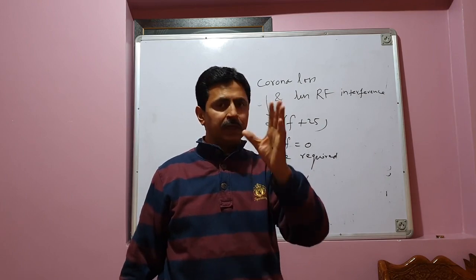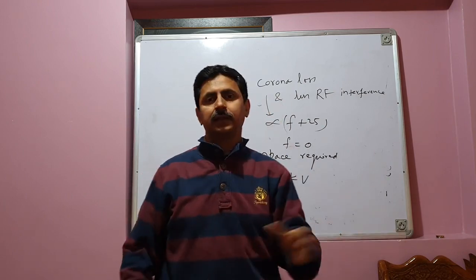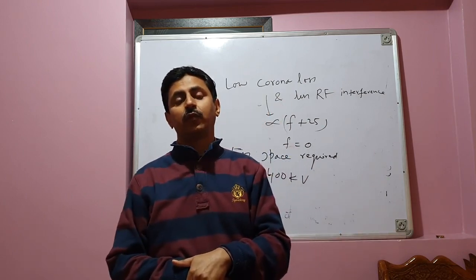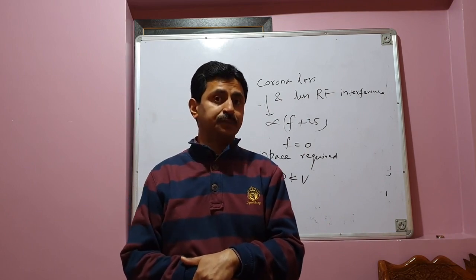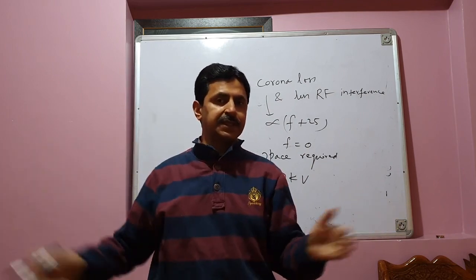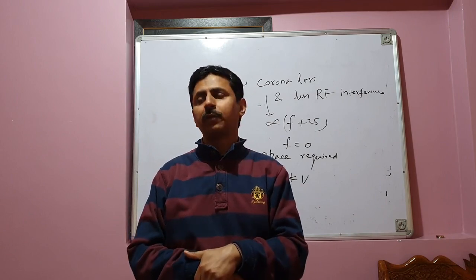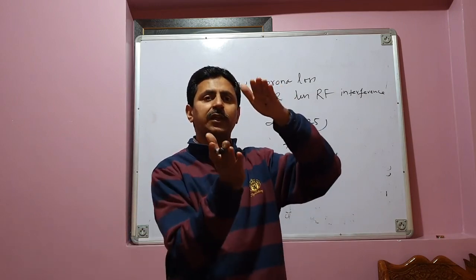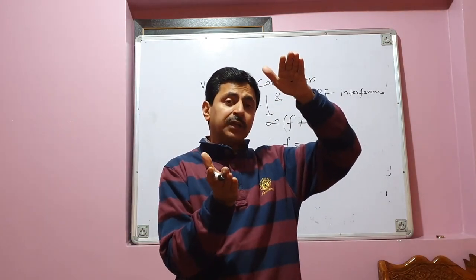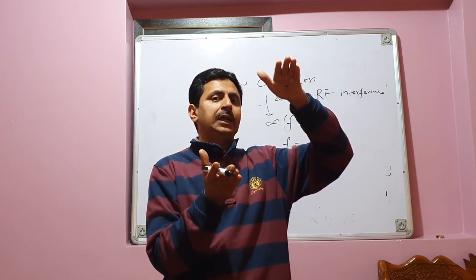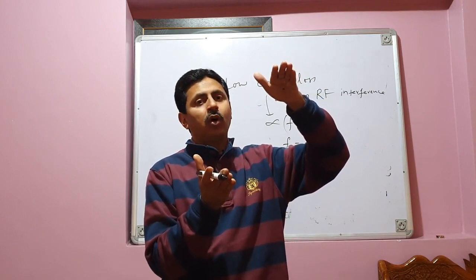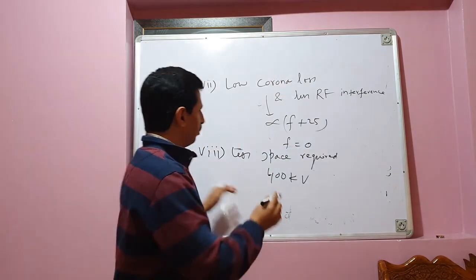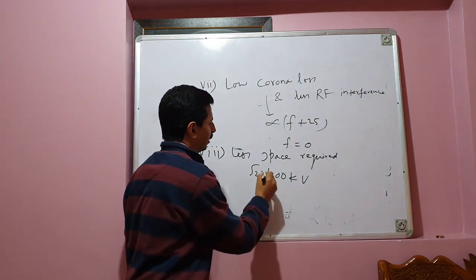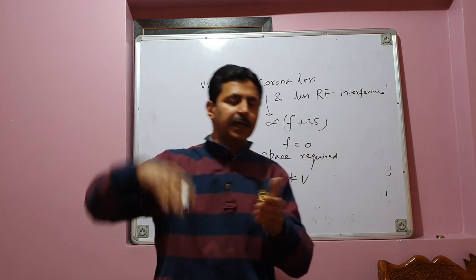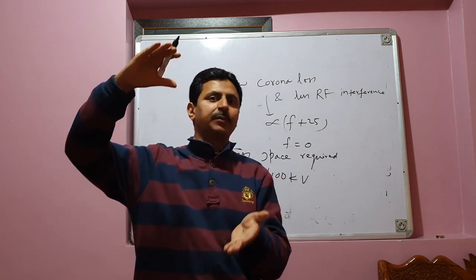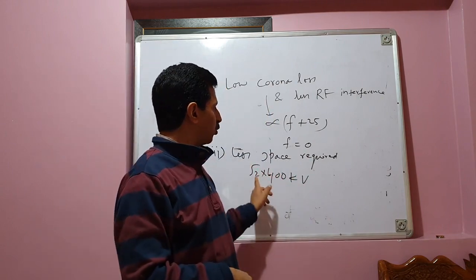So in this case, the insulator has to be designed for 400 × √2. 400 kV, it's AC, this is the RMS value. And what will be the peak? You have to design your insulator not for the RMS value of voltage. You have to design the insulator for the peak value of voltage, and peak value of voltage means you have to multiply it by root 2. So therefore, the insulators of the transmission lines have to be designed for root 2 times 400 kV.